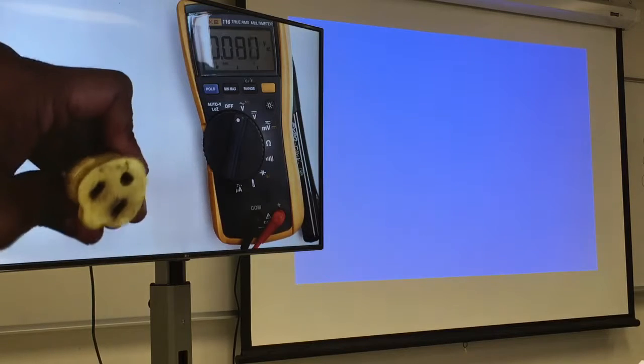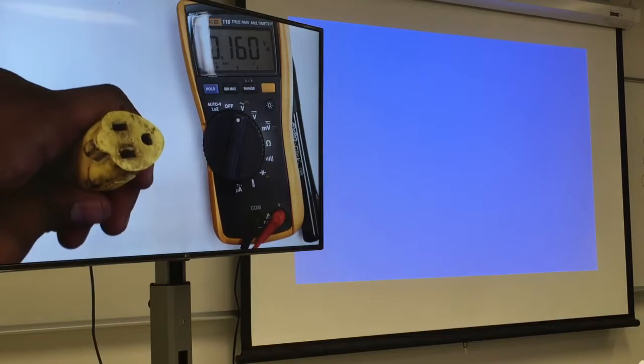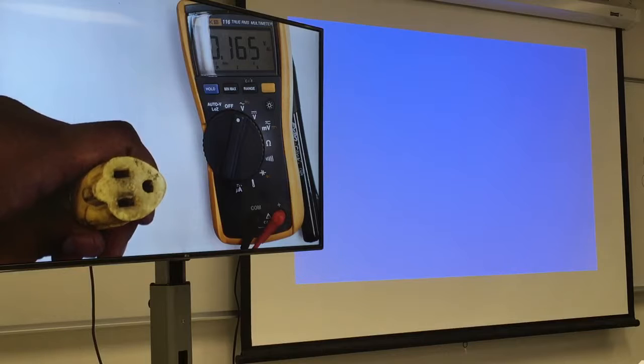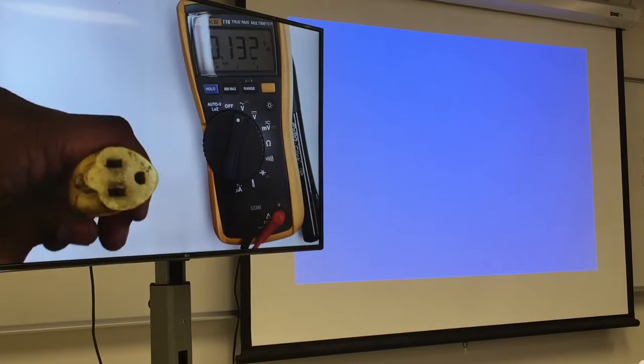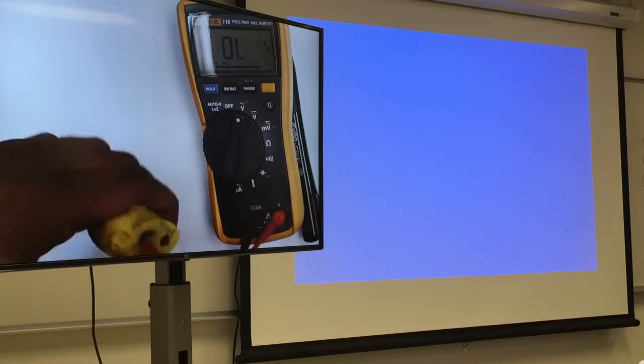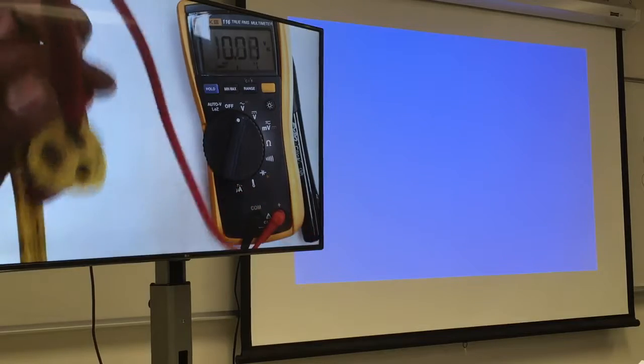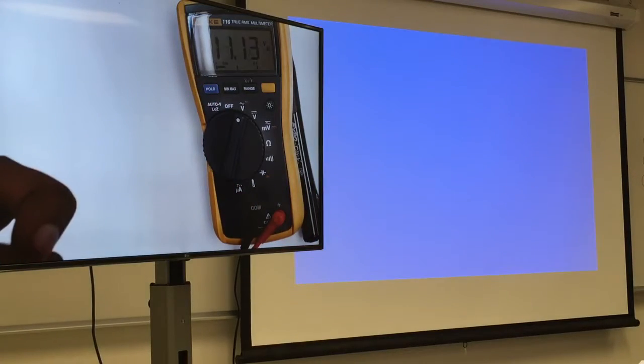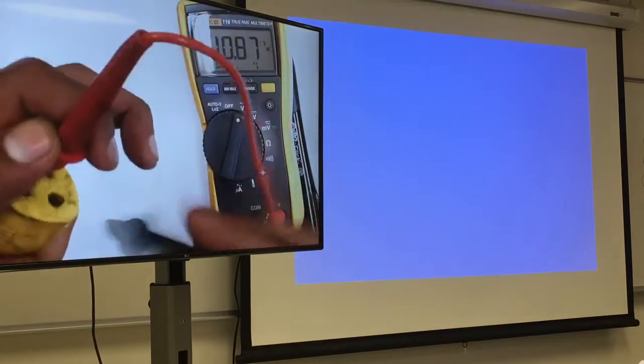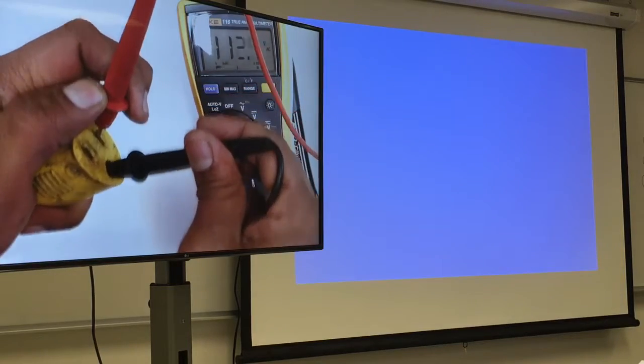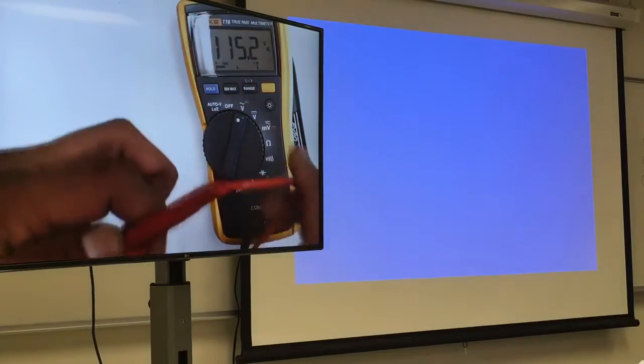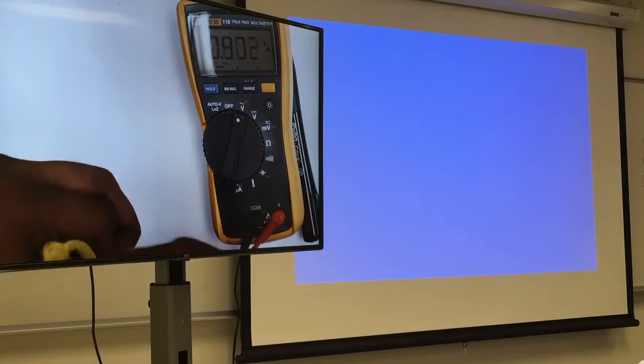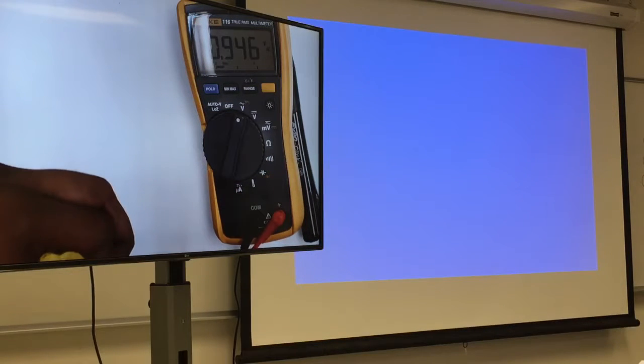What is the other way to do it, if it's not convenient? If you go there and the neutral is covered up, there's nowhere to plug in. I'm gonna put one probe in the hot, and one on a piece of metal, which is the ground. I still get 115. If I put it between the neutral and the ground, I get nothing, about 0.9 volts, which is basically nothing.